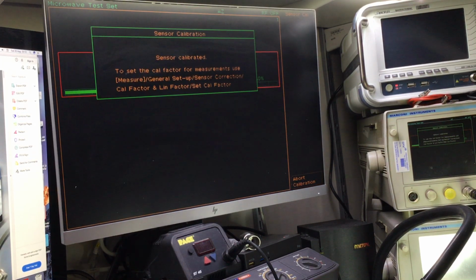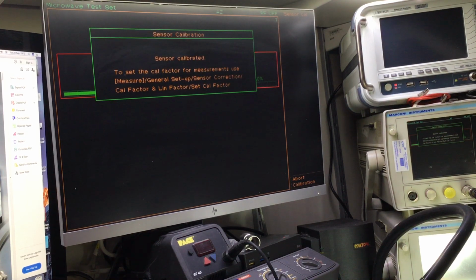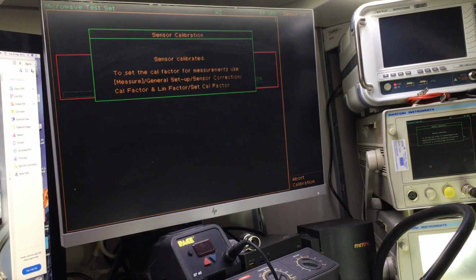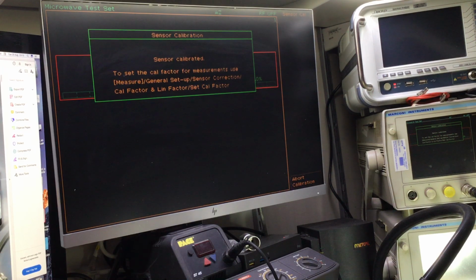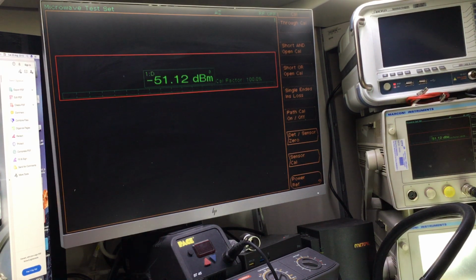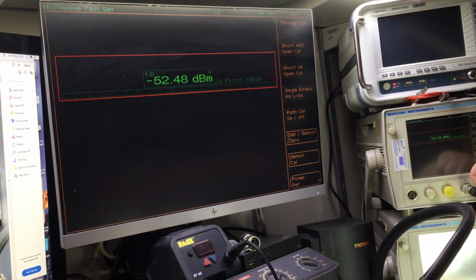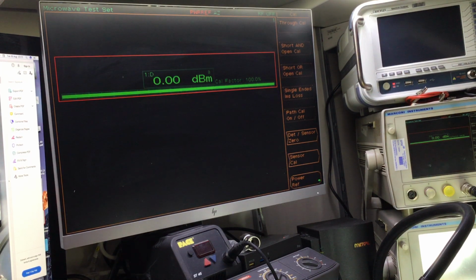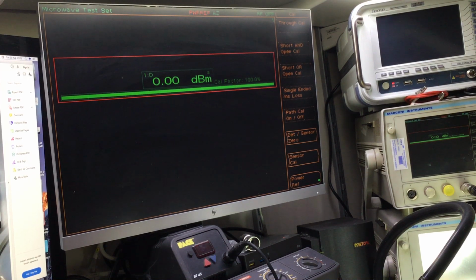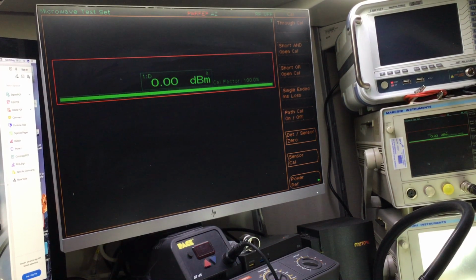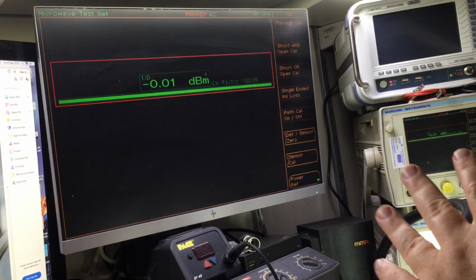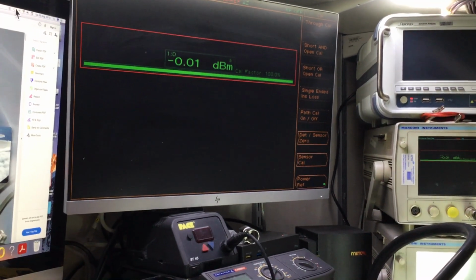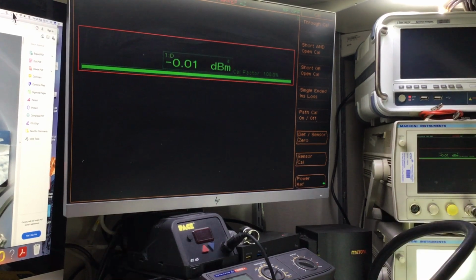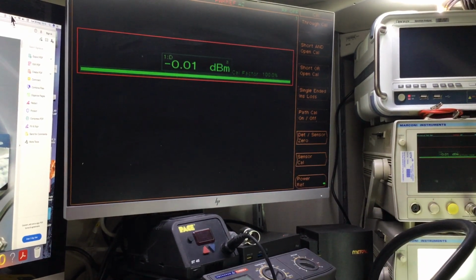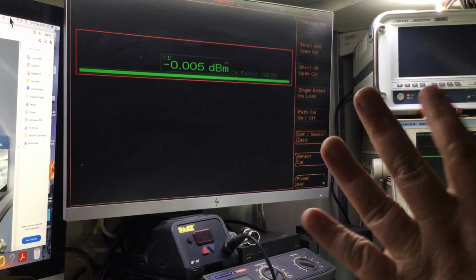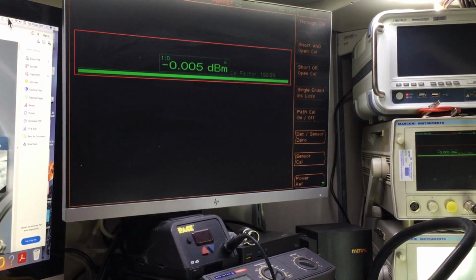So there we are, it's all done. It says sensor calibrated, so we've done that particular thing already, so that's great. Now when I put the sensor power on, we should be getting 0 dBm, and that's what we're getting, 0 dBm. So this microwave test set is actually fully calibrated. It's not out of cal, it's all in cal. It's been calibrated, so we know that's going to be a good reference starting point.